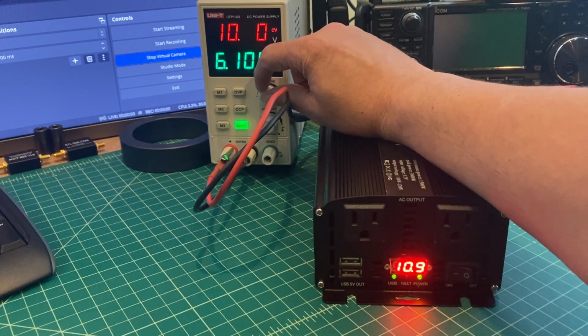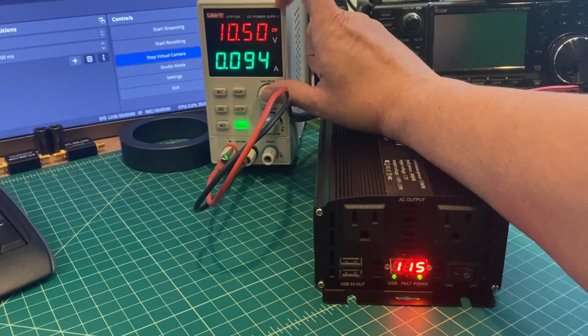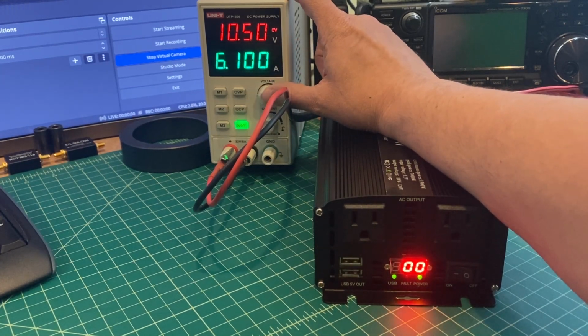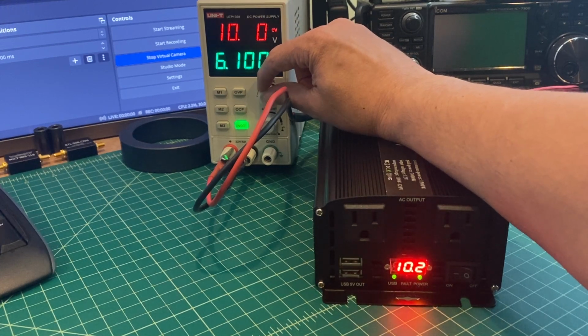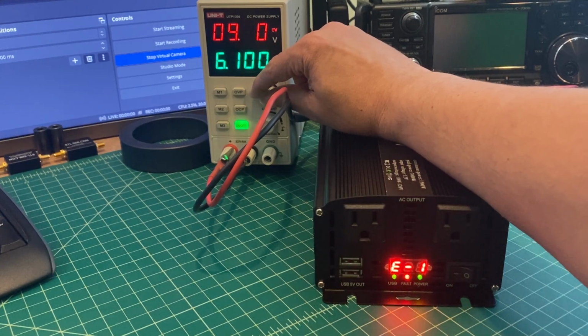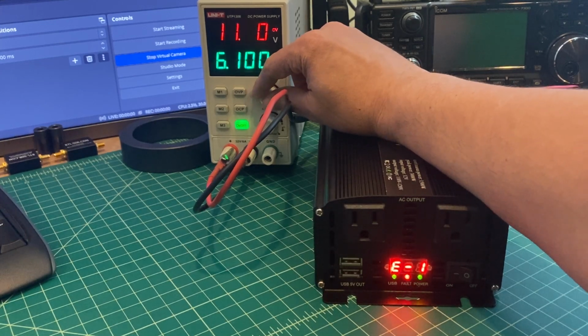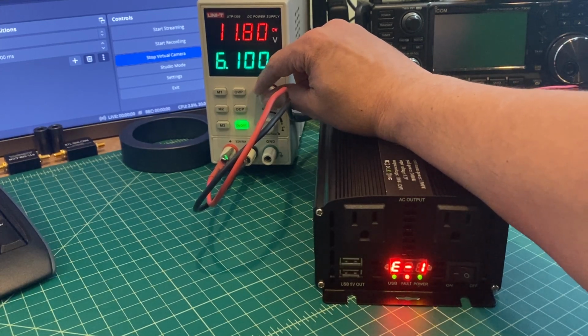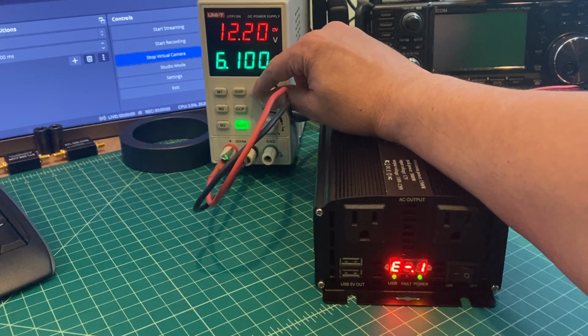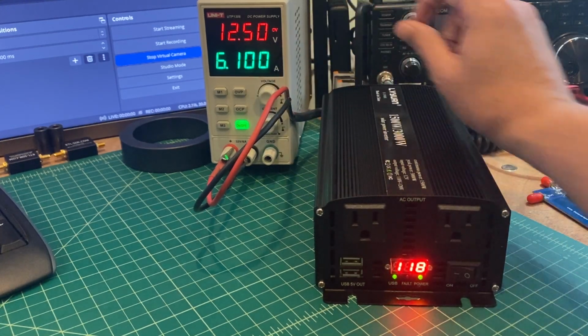Now let's go test the low voltage protection. We're getting the alert now at 10.5, but I think we need to go down below that for it to fail. And then there's the failure at 9.8, 9.9. So there's a little bit of a difference between what the power supply says the output voltage is versus what's being received into the inverter, and that could be due to the condition of my connectors.